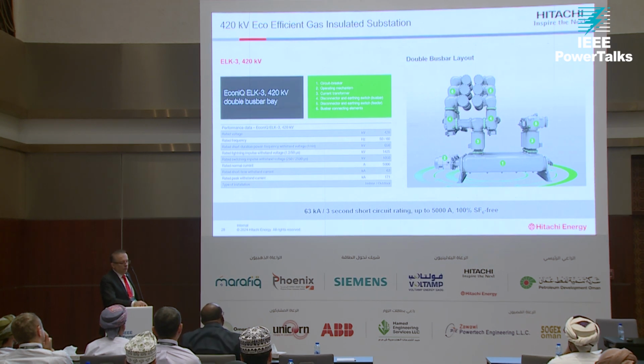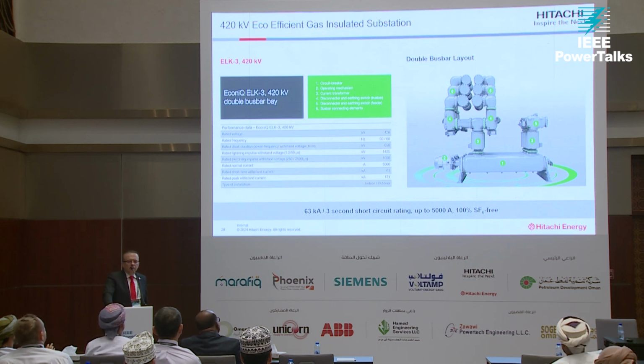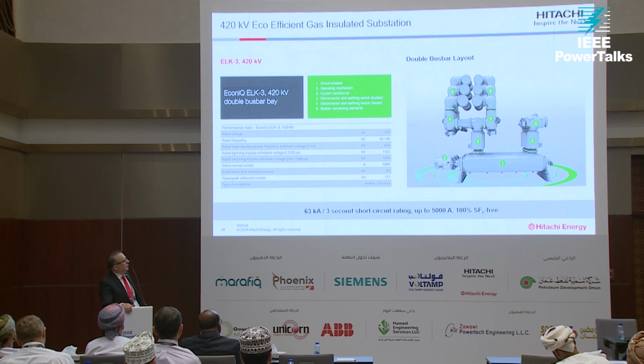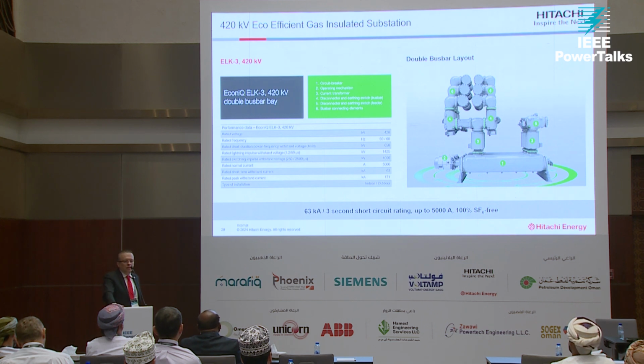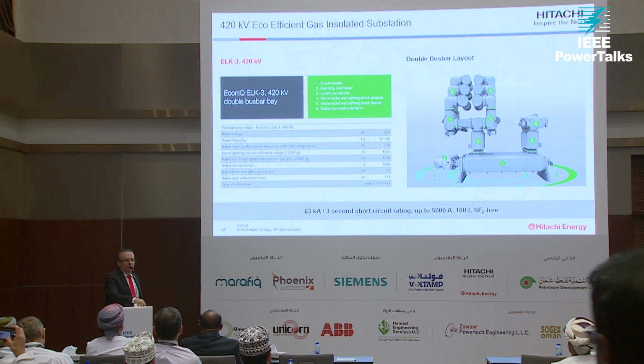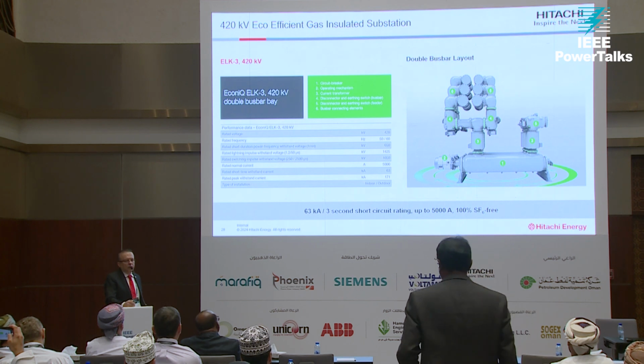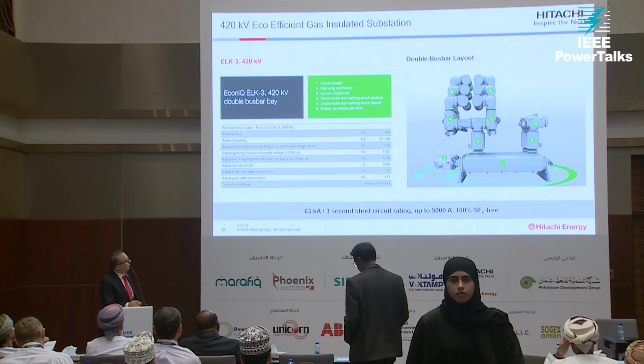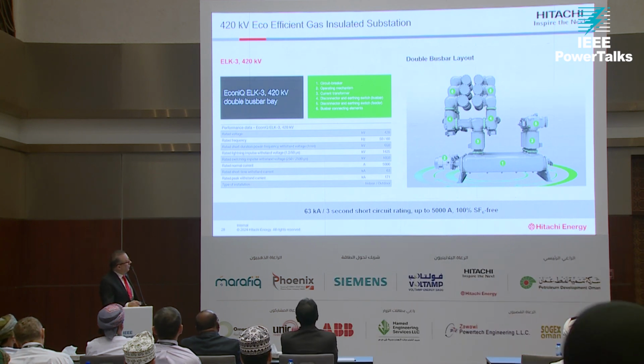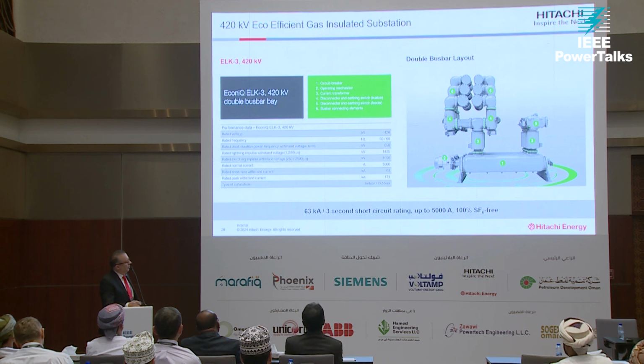Here is our 420 kV product. When it comes to electrical characteristics, we have the same characteristics as the old SF6—short circuit rating, rated current, and so on. We can have indoor or outdoor versions. It's essentially a one-to-one replacement, and we already have this product installed in many utilities. Short circuit rating is 63 kiloamps for 3 seconds.